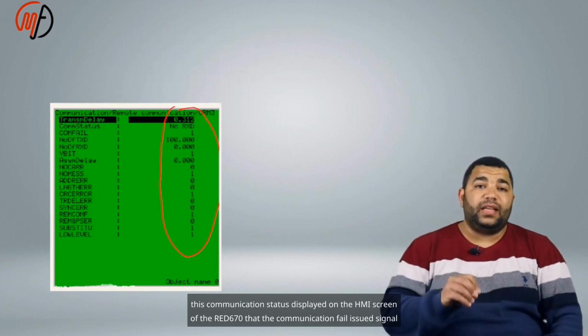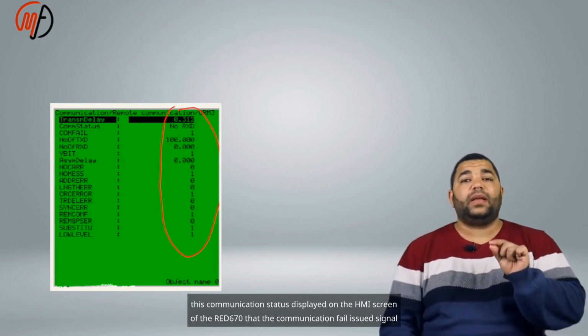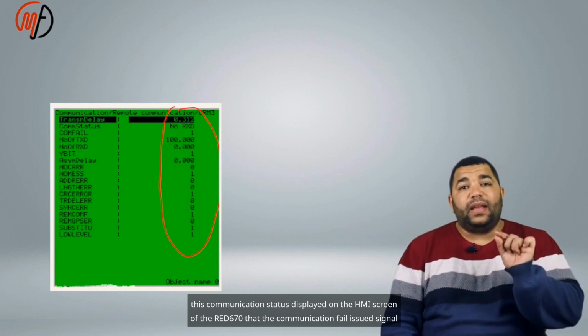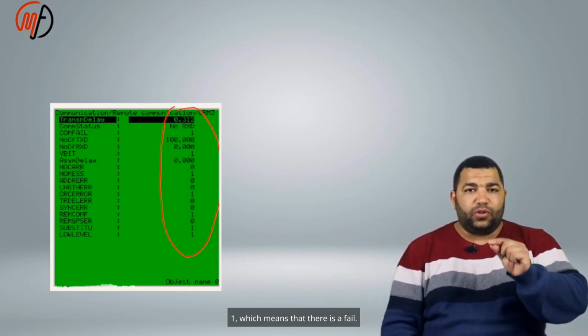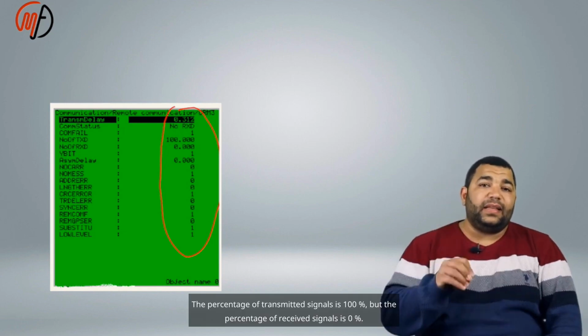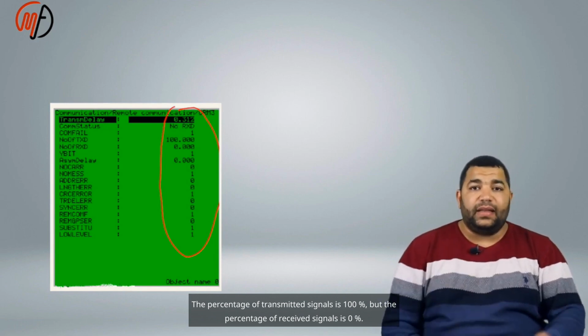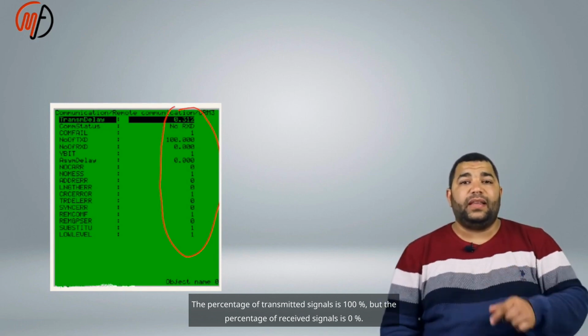Notice in this communication status displayed on the HMI screen of the RED670 that the communication fail issued signal 1, which means that there is a fail. The percentage of transmitted signals is 100%, but the percentage of received signals is 0%.